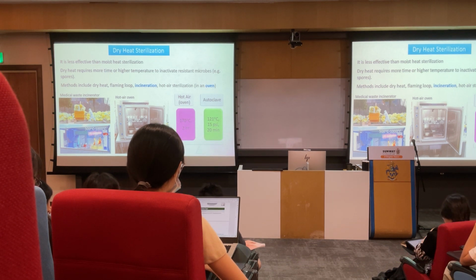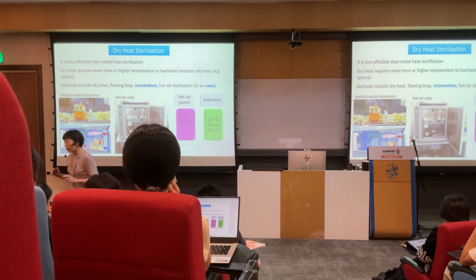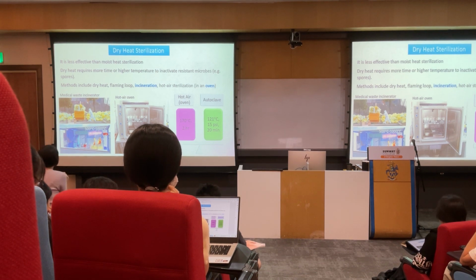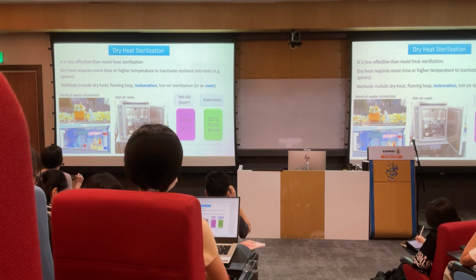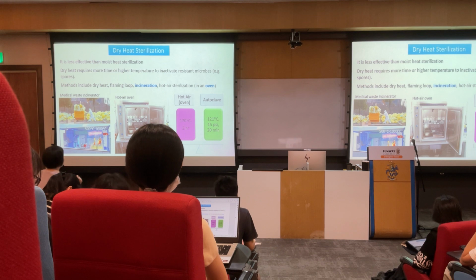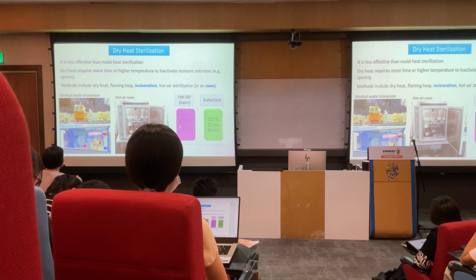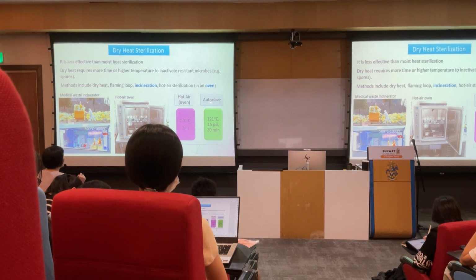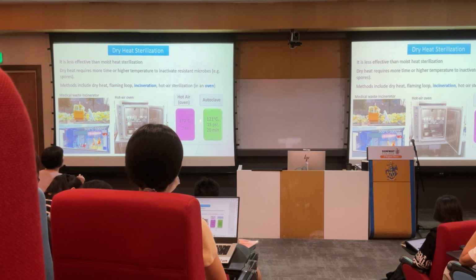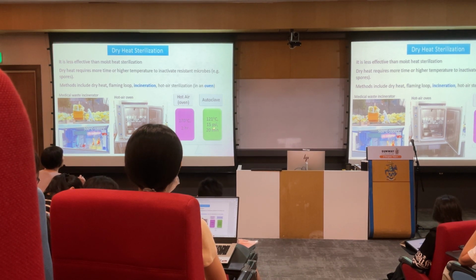Dry heat. Using the heat, but this is a dry heat, no water involved. So dry heat is less effective. Imagine that dry heat is like an oven. For example, an oven also provides hot air. You can increase the heat inside the oven to 170 degrees Celsius, but it would require 2 hours. Compared to an autoclave, the same effectiveness can be achieved if you only apply 120 degrees Celsius for 20 minutes. So that's the difference. You take a longer time and a higher temperature, using the dry heat to kill the microorganism.